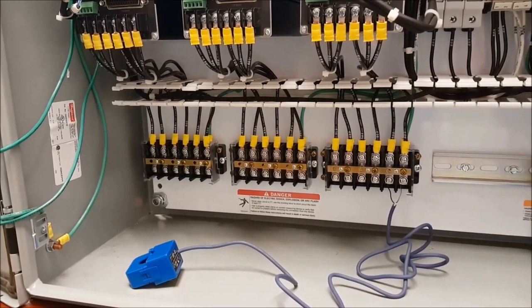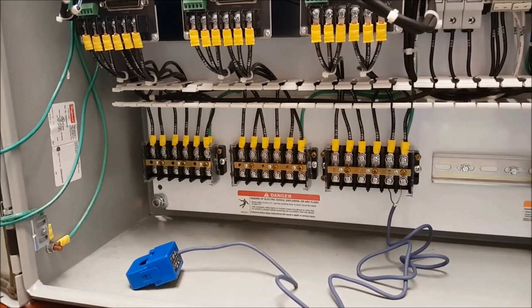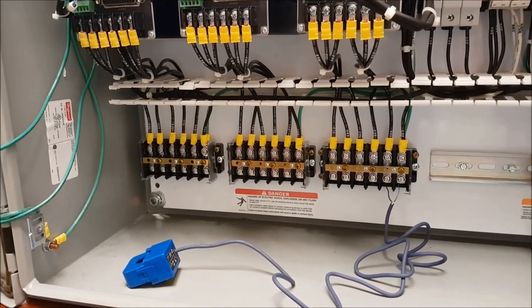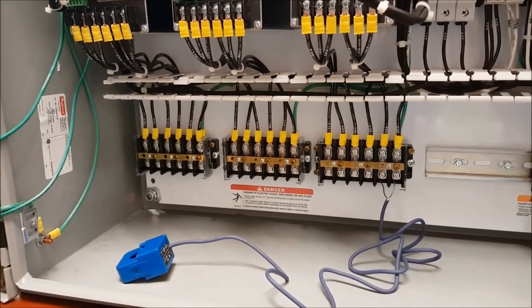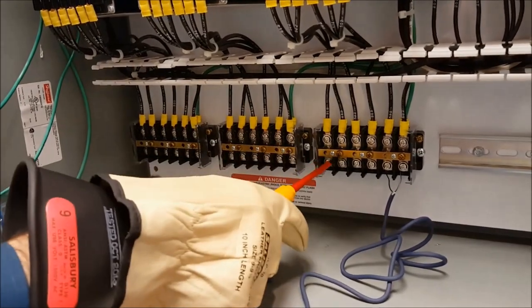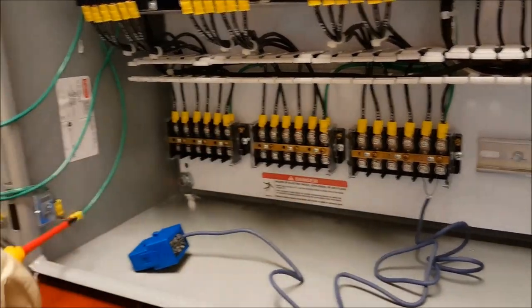CT shorting blocks are wired such that the negative leads of the current transformers are connected to the same node and tied to ground. Here, here, here, which is then tied to ground.